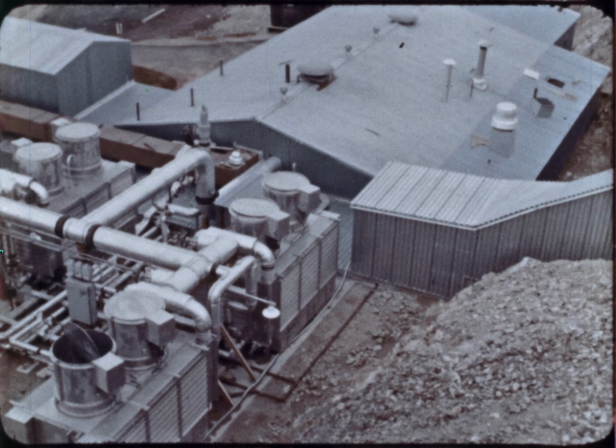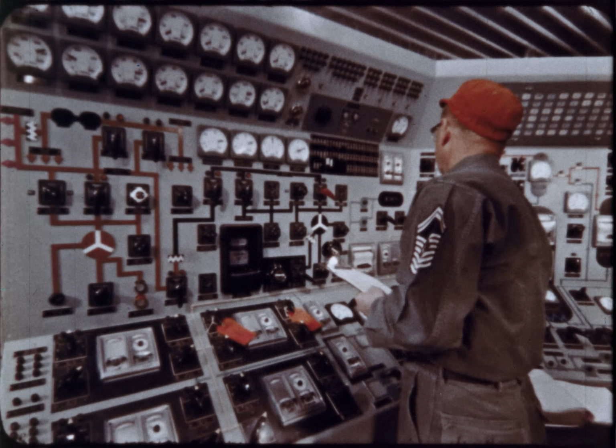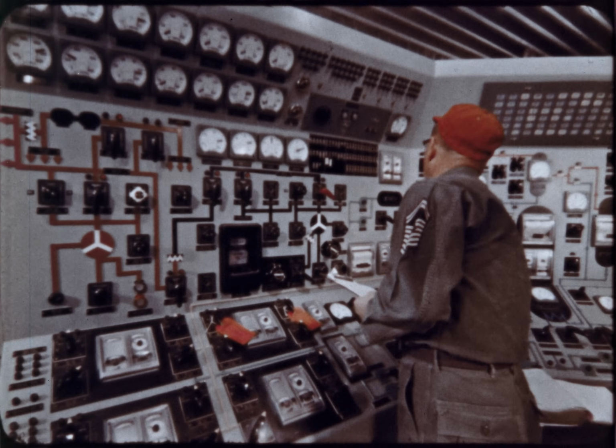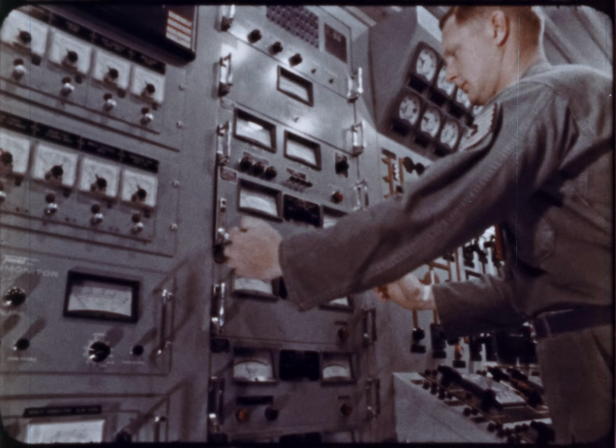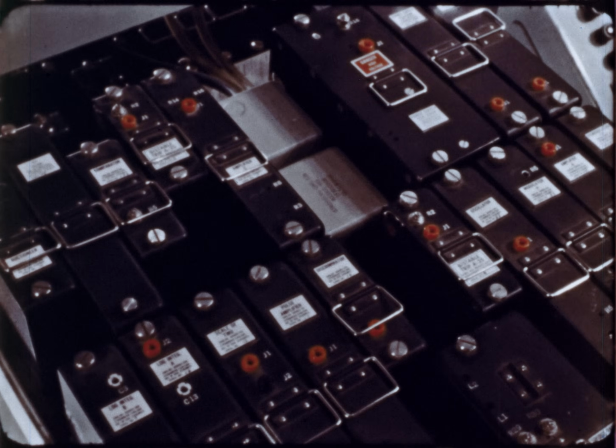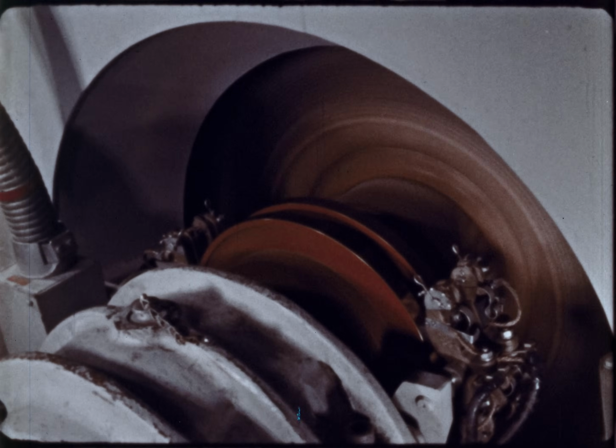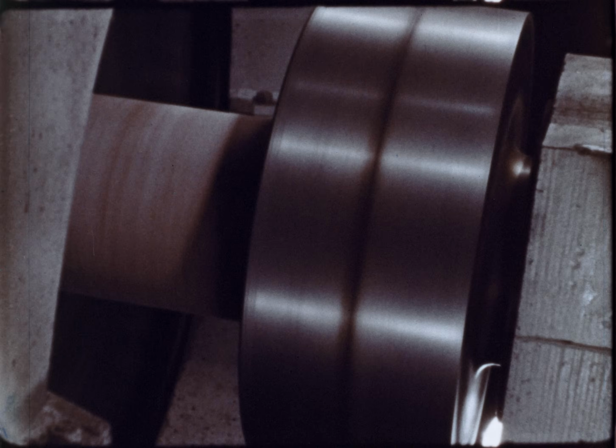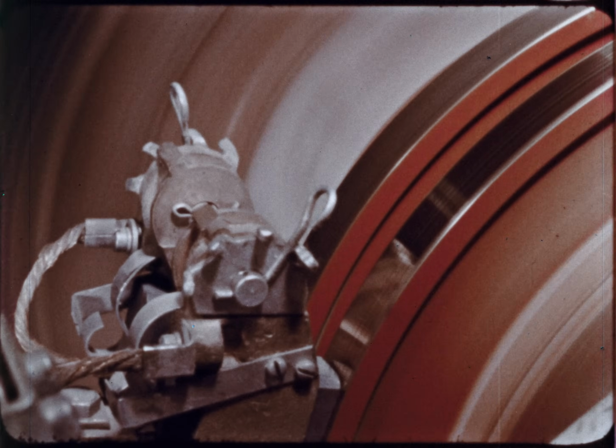The secondary system contains 9 packages. The control room package contains the console from which the plant is run by a single controls operator. These controls must meet a reliability specification of 99.45%. Consequently, solid-state components are employed. The turbine generator package houses the equipment that converts to electrical energy the heat generated by the reactor core. The generator produces 1,250 kilowatts gross output.